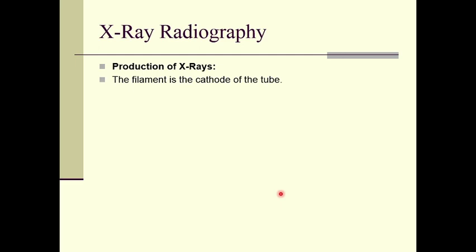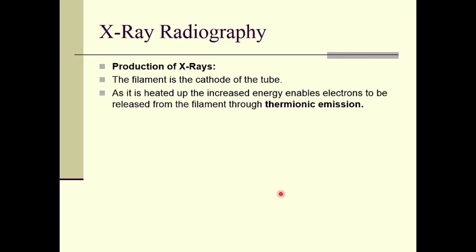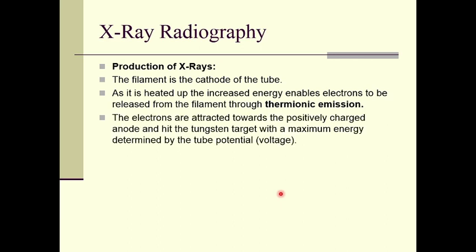Let us study the production of X-rays. X-rays are produced inside the Coolidge tubes. The filament is the cathode of the tube. As it is heated up, the increased energy enables electrons to be released from the filament through thermionic emission. The electrons are attracted towards the positively charged anode and hit the tungsten target with maximum energy determined by the tube potential or voltage.